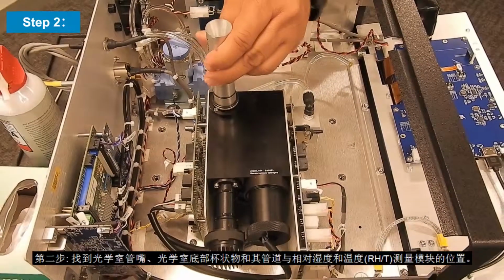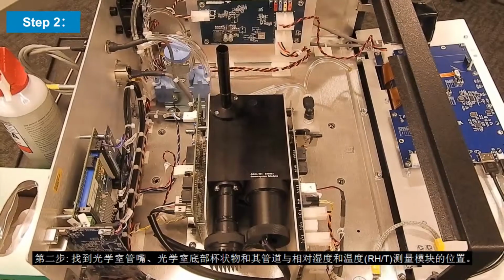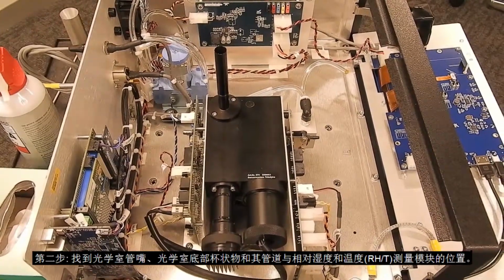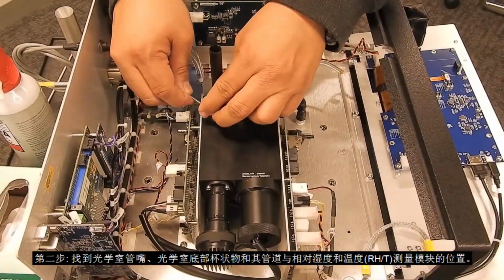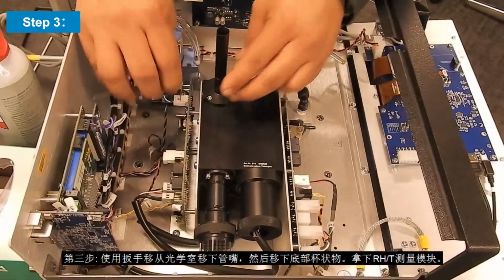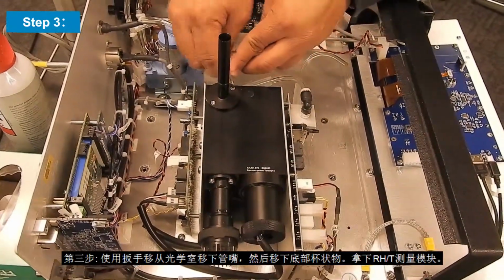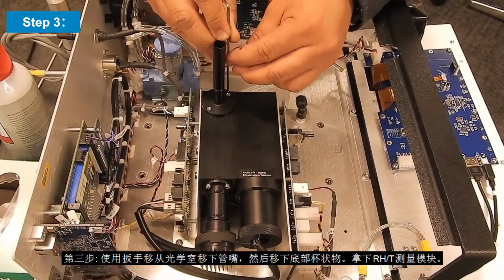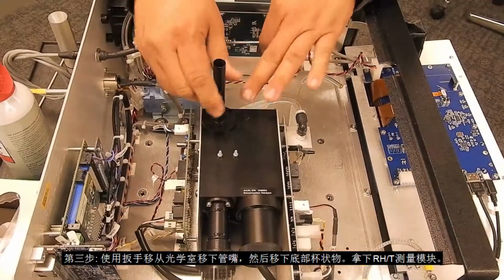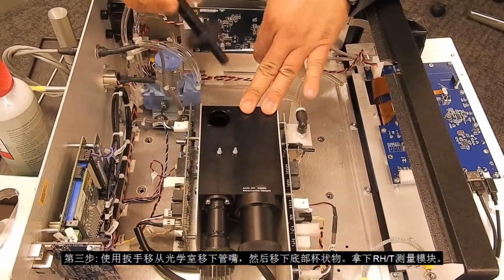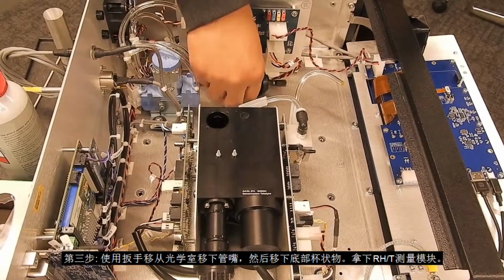Step 2. Locate the optical cell nozzle, the cup at the bottom of the optics chamber and its tubing, and the relative humidity and temperature sensor. Step 3. Remove the optical cell nozzle from the optics chamber using an Allen wrench and detach relative humidity and temperature sensor tubing from the cup.